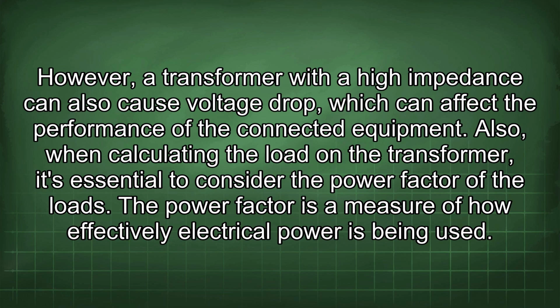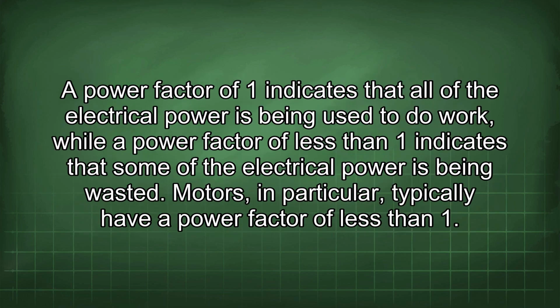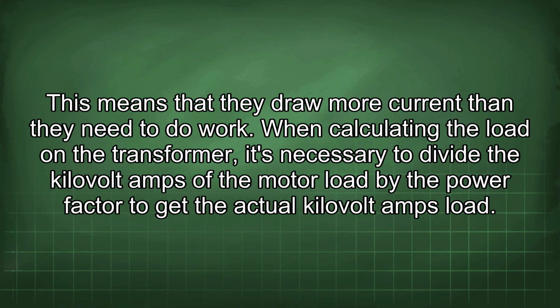The power factor is a measure of how effectively electrical power is being used. A power factor of 1 indicates that all of the electrical power is being used to do work, while a power factor of less than 1 indicates that some of the electrical power is being wasted. Motors, in particular, typically have a power factor of less than 1. This means that they draw more current than they need to do work. When calculating the load on the transformer, it's necessary to divide the kilovolt amps of the motor load by the power factor to get the actual kilovolt amps load.